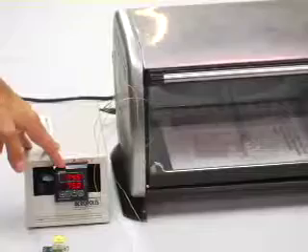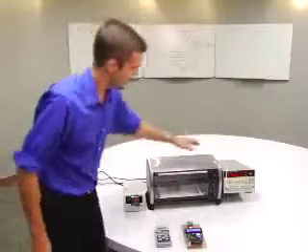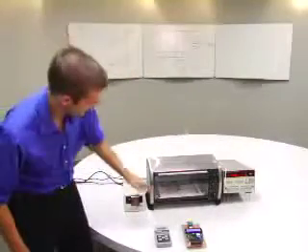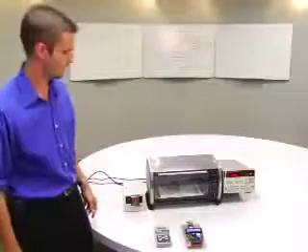We've also got a specially modified toaster oven with a PID controller that gives about 0.1 degree centigrade stability to make it a little more useful for calibration purposes, and a quartz resonant thermometer to compare both of these against. And inside the oven we've got the quartz probe and two thermocouples all in close proximity.